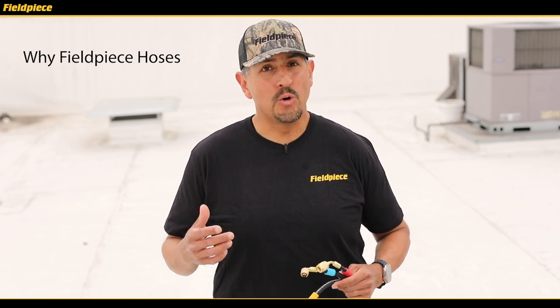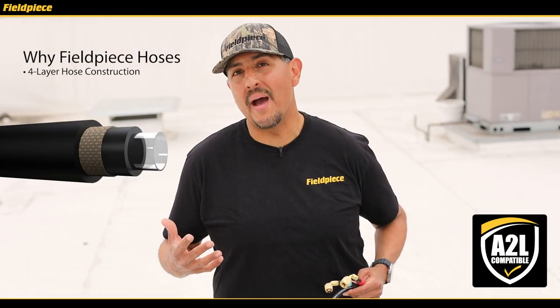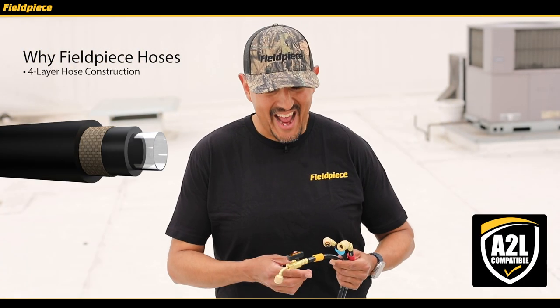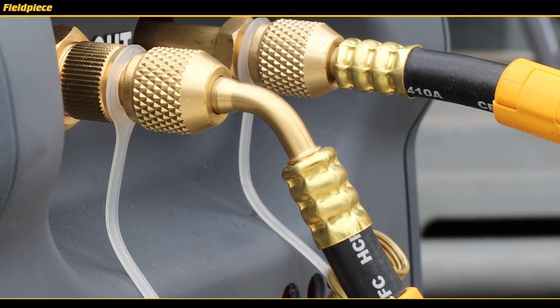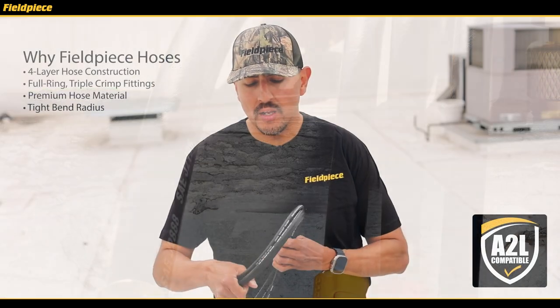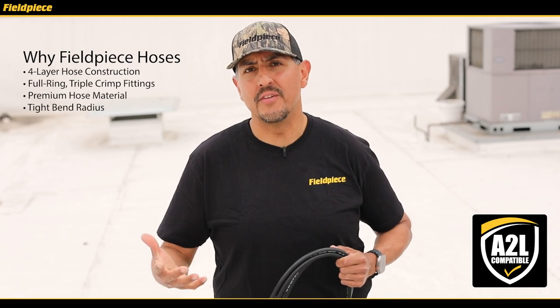Well, number one they're really cool and they say Fieldpiece on them, but number two they're designed with a four-layer construction to make them compatible with A2L refrigerants, and they have a triple ring crimp fitting to give extra sealing redundancy in the field. All the Fieldpiece hoses are constructed with a premium black hose material that feels really soft in the hand and has a really good bend radius even in wide ranging temperatures in the field.